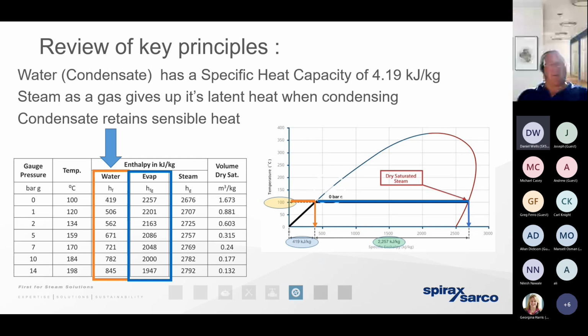And from an energy efficiency perspective, that's critically important. Simply put, if we don't have dry saturated steam, the steam could exist in the wet steam zone. The problem that results from an energy efficiency perspective is that we're going to get more heat loss in the infrastructure. We could be generating 10,000 kilograms of steam per hour in the boiler, but fail to get anywhere near that at the heat exchanger. So, of course, the boiler has got to work harder to overcome that inefficiency.